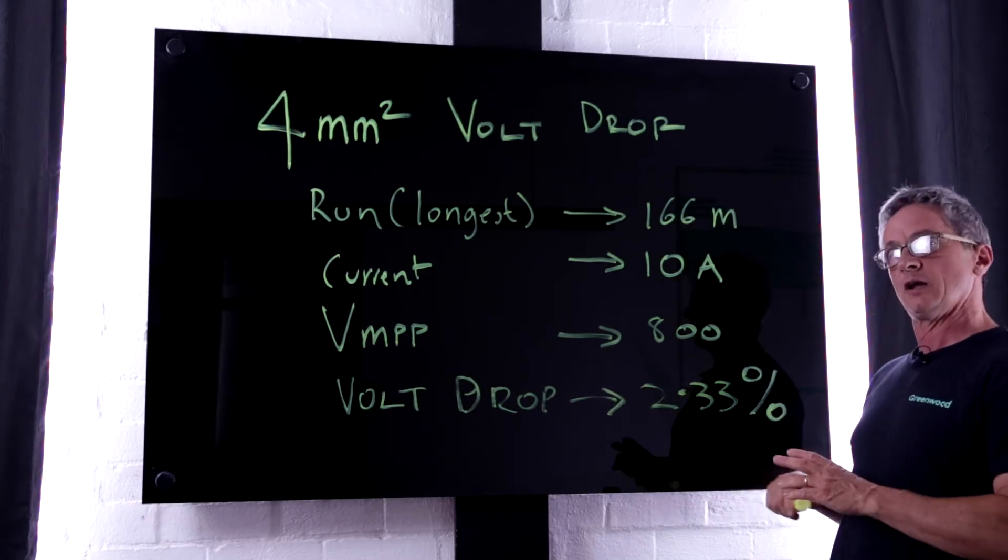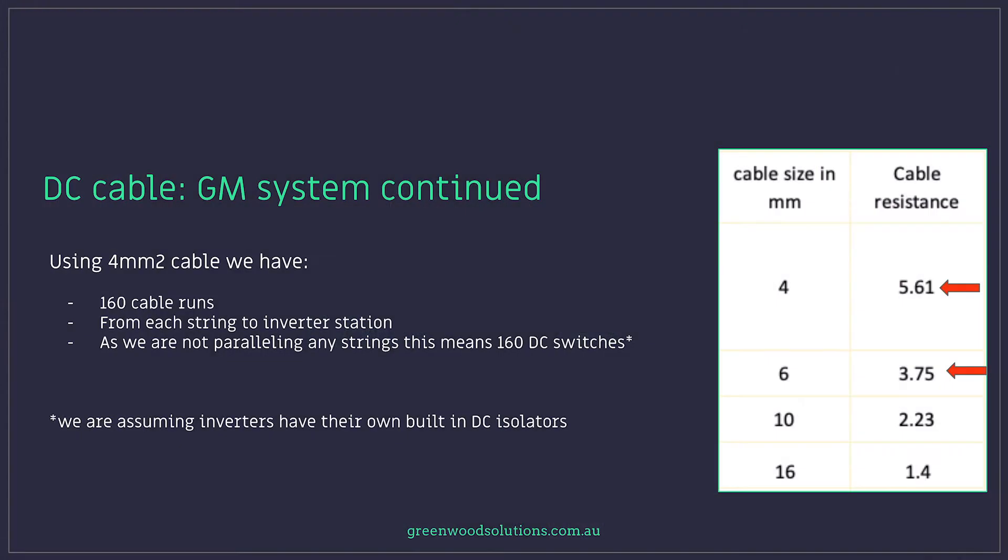We're getting up pretty close to that 3%. Using 4mm cable we have 160 cable runs from each string to the inverter station. As we are not paralleling any strings this means 160 DC switches and we are assuming the inverter have their own built-in DC isolators or DC switches.